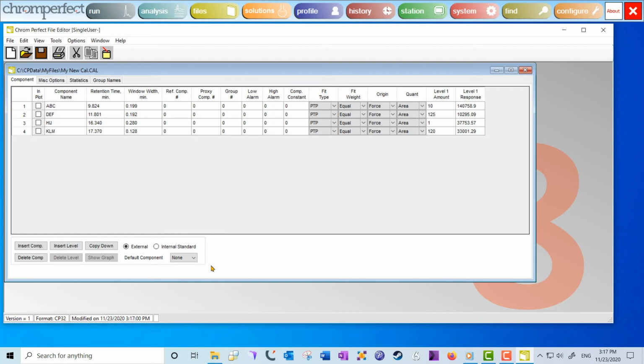Unidentified peaks are peaks that are not listed as components in the calibration file. They are not deliberately in the calibration standard. Nevertheless, it is often desirable to calculate amounts for these peaks, for example in petroleum analysis, where the number of peaks greatly exceeds the number of standards.